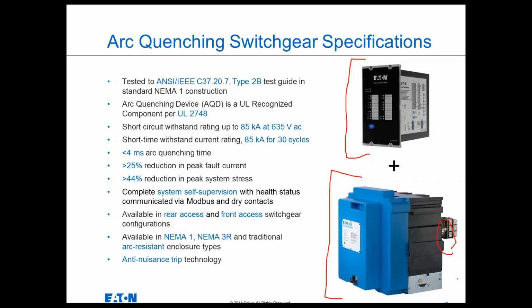So the arc detection relay and the arc quenching device work in concert to provide that incident energy reduction that I described. So the system in Magnum switchgear has been tested to that arc resistant test guide. So it can pass the test guide in standard NEMA 1 construction, so no ducts, plenums, none of that reinforced enclosure. The arc quenching device is compliant with this brand new UL 2748 standard for arcing fault quenching equipment. So just a safety standard that UL has developed to govern these products.